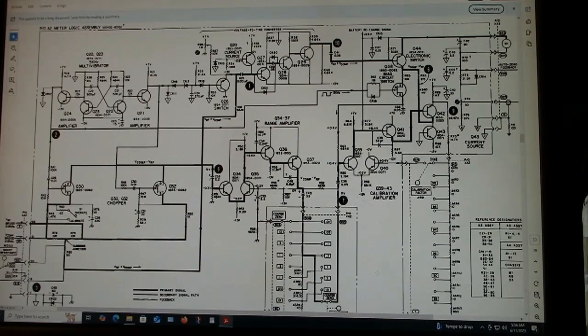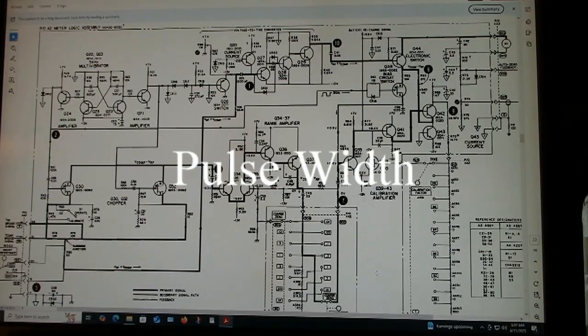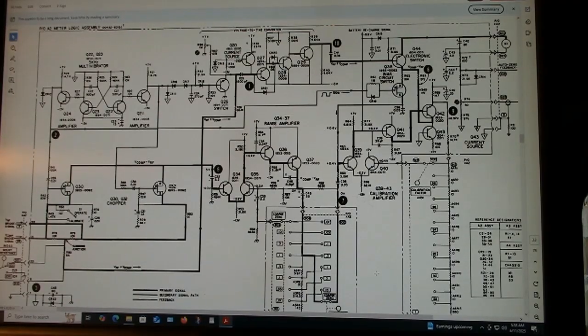Now to produce the V comp plus VRF signal, they're summed together. Here's where they come in on the left. They're summed together through these two 10K resistors, and they're applied up here to a voltage to time converter. This is also driven by this 5 kilohertz multivibrator that's produced by Q23 and Q22. The voltage to time converter produces an output pulse signal whose width is proportional to the sum of V comp plus VRF, and that output is fed here to the electronic switch. The output of the electronic switch produces 5 kilohertz pulses. The amplitude is proportional to V comp minus VRF, and the width is proportional to V comp plus VRF. And the output here is fed into the metering circuit.